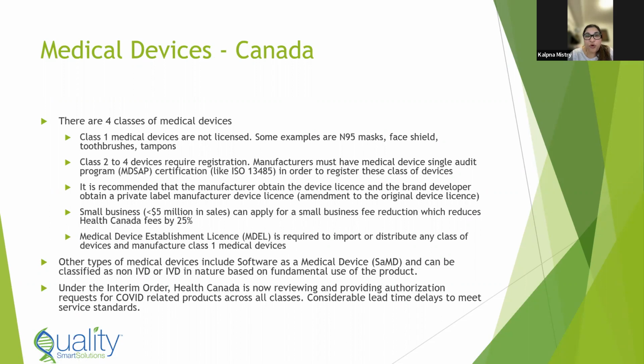Class two to class four require a registration, and this can be associated with MDSAP, or a Medical Device Single Audit Program certification, which is equivalent to the ISO 13485 for medical devices in order to register these classes of devices. Class two to class four vary in the type of requirements you need for quality, efficacy, and safety data as well. So that's just a broad overview to give you an idea of that.